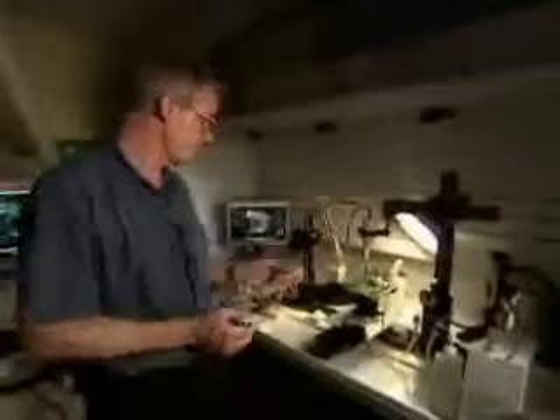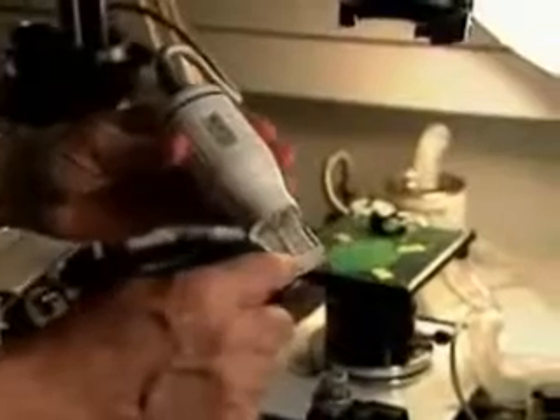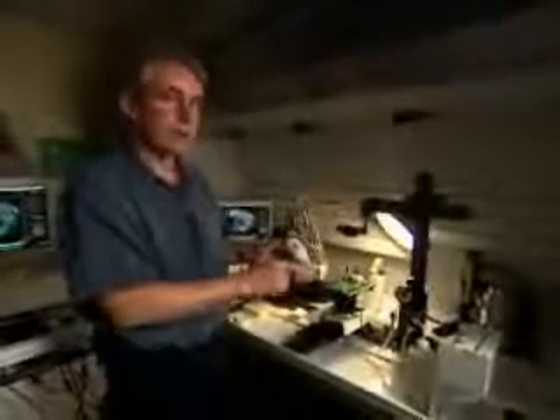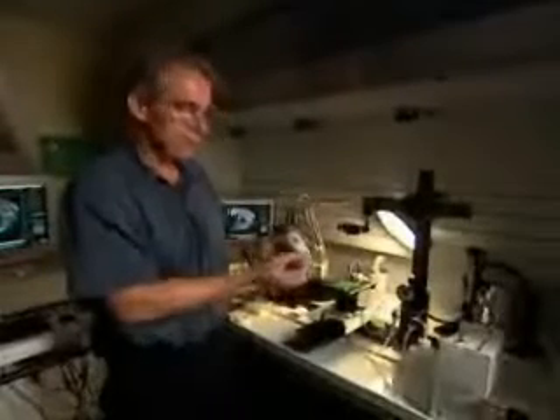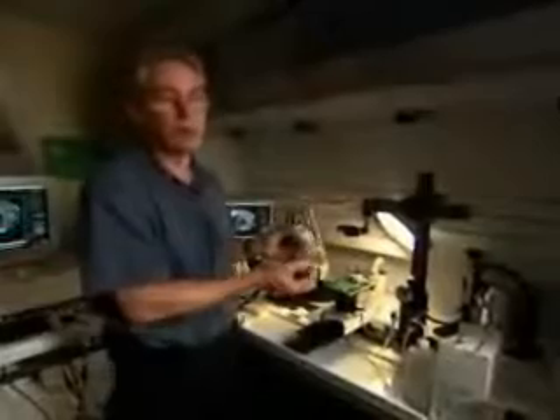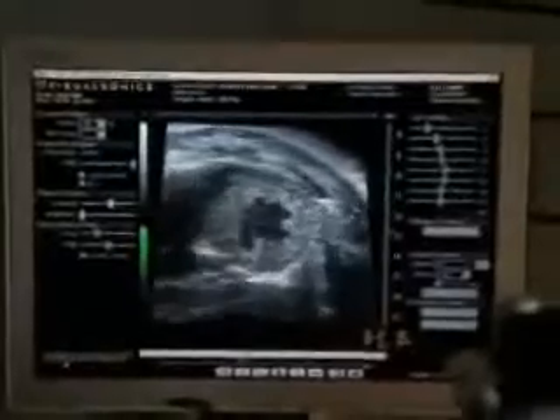The kernel of the innovation in this particular apparatus is the transducer, and that's a device that transmits and receives the ultrasound. So let's go have a look. The critical component of this system, and the part that holds most of the innovative components, is this little thing over here called the scan head. And this device is what actually transmits and receives ultrasound from the mouse that we're trying to study. Essentially you can view it as a flashlight for ultrasound. It creates a very small ultrasound beam with a width smaller than a human hair that essentially propagates out from this transducer into the tissue and receives the echoes back from the tissue to create the image, and creates images anywhere between 30 frames per second up to 300 frames per second.